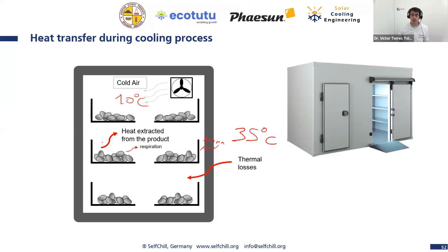So we have already 3 factors, right? 1, 2, and 3. The heat from the products, the respiration of the product, and the thermal losses. These we all need to consider for the design of a cooling system, of a cold room. But this is not all. We have also other things. We have, for example, air infiltration. What about when you open the door? Then you are getting humid, warm air inside the cold room that is going to cause a cooling load. So this needs also to be considered.